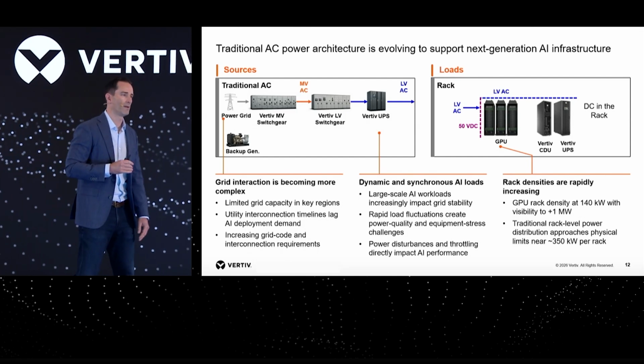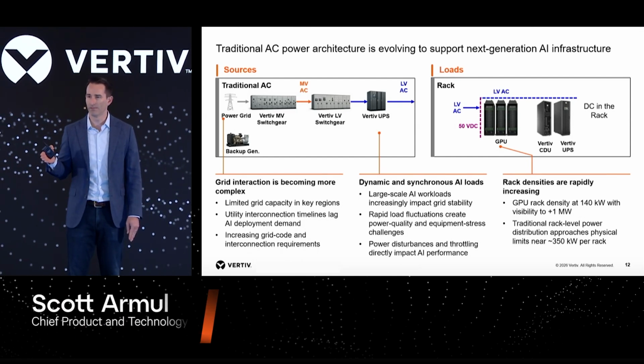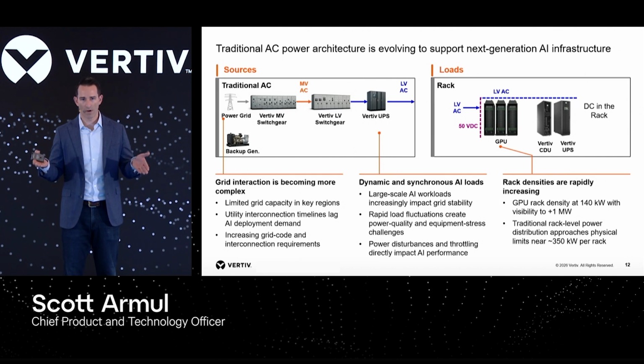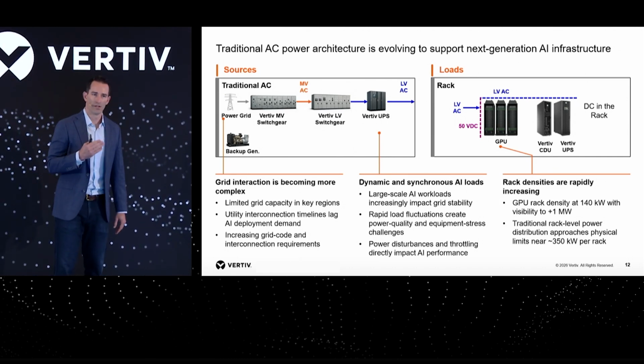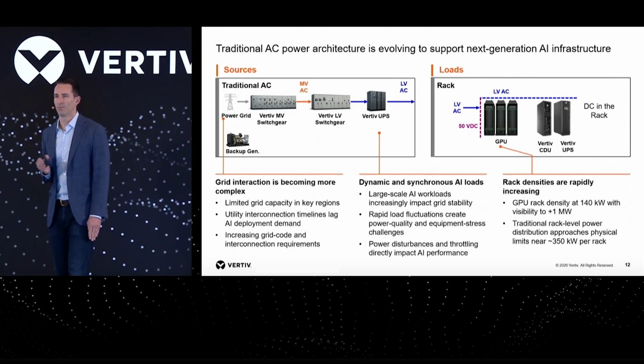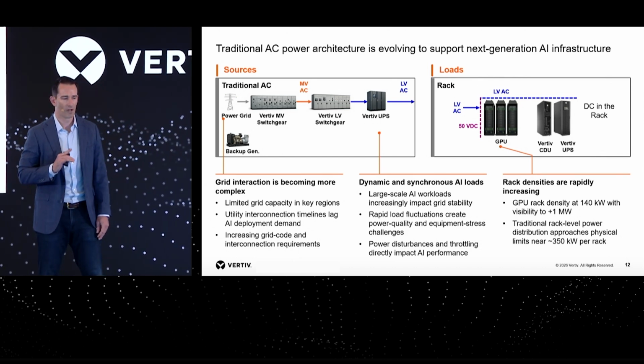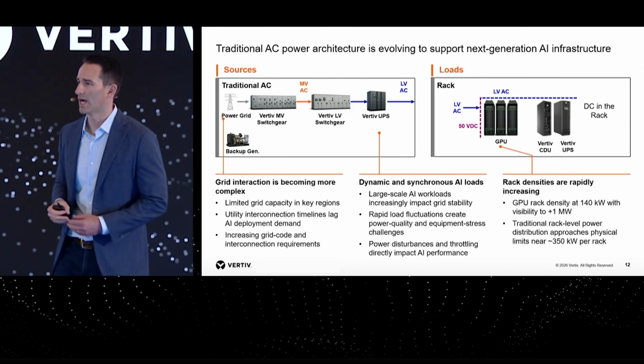Current GPUs today are deployed with AC power fed in, conversion at the rack level to 50 volts DC, and that's how we get to operation at a GB200, GB300, choose your GPU type of performance today. And then from a rack density perspective, we highlighted this.